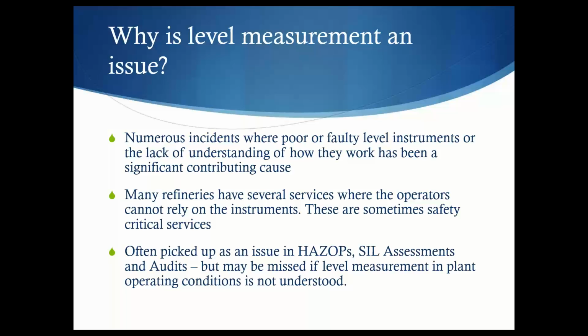So now I'm going to go a bit more into why level measurement's an issue. We've already established there's people still having those incidents out there. A number of times the incident findings have found poor or faulty level instruments, or the lack of understanding of how they work, has been a significant contributing cause, as it says here.